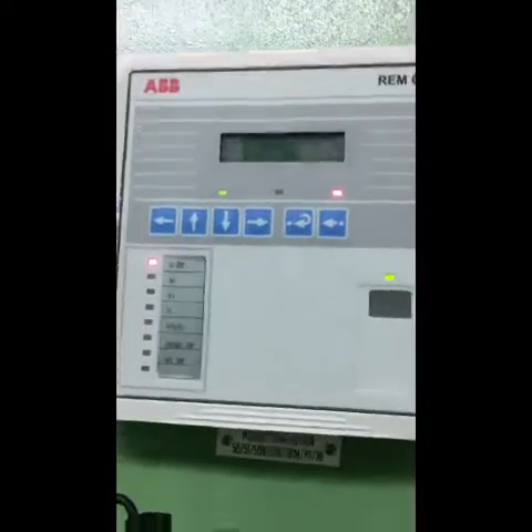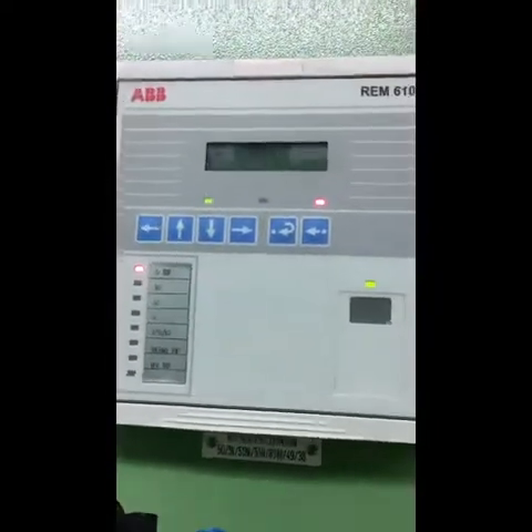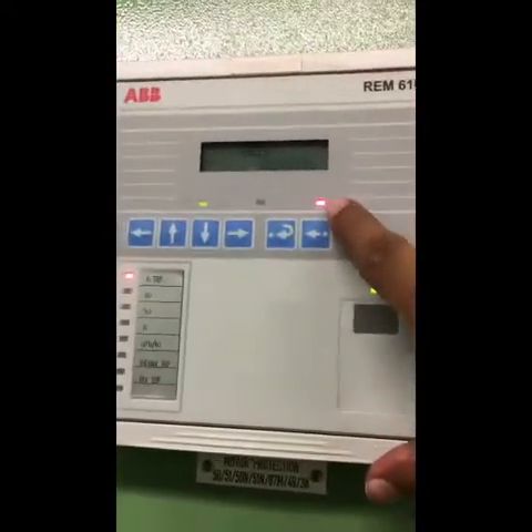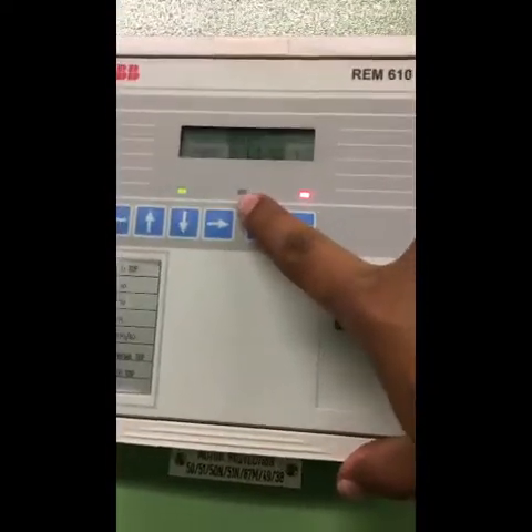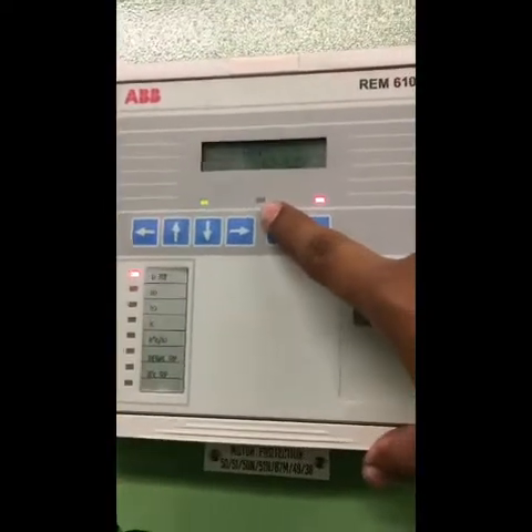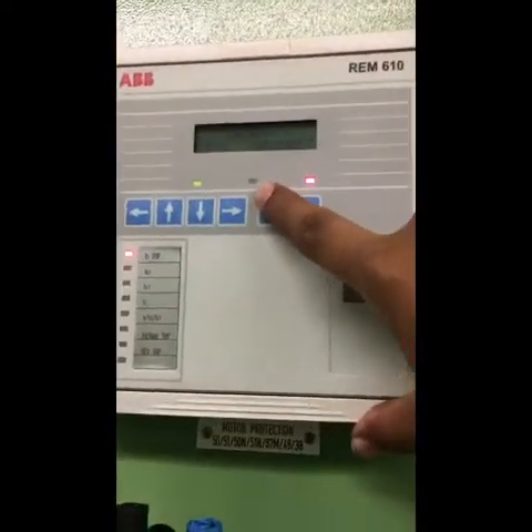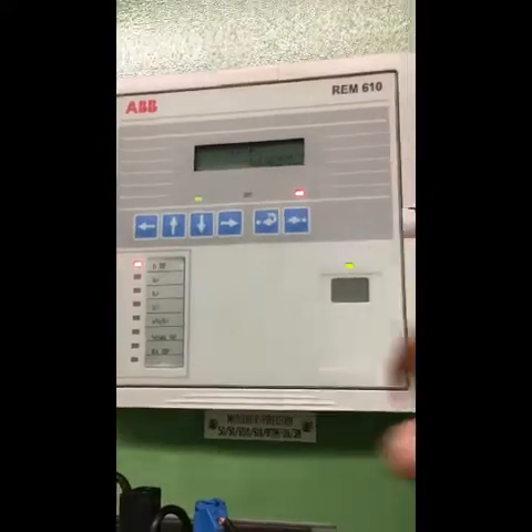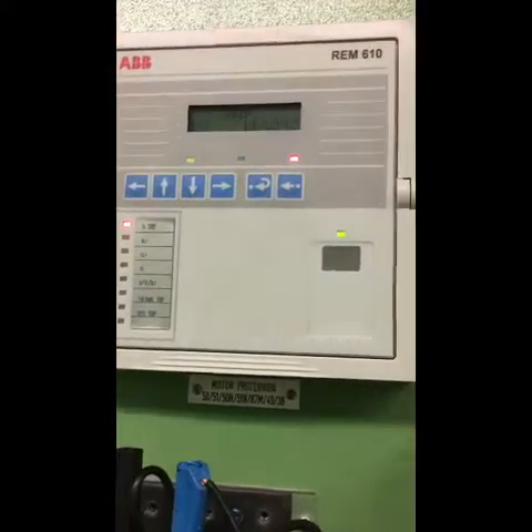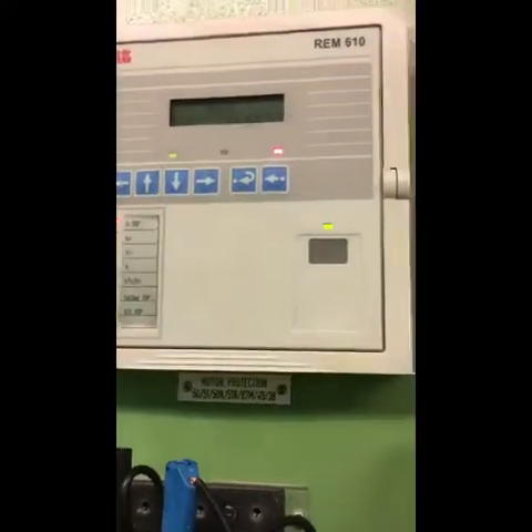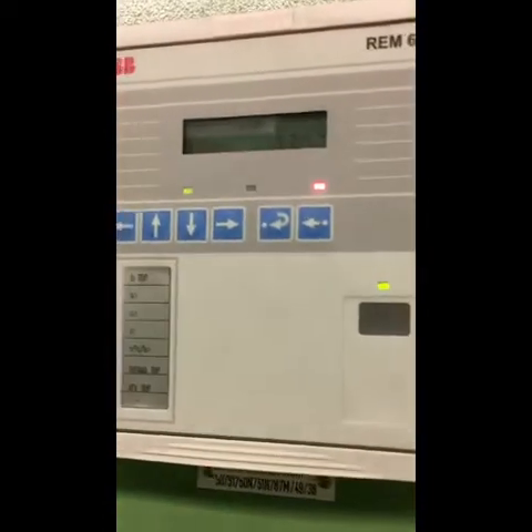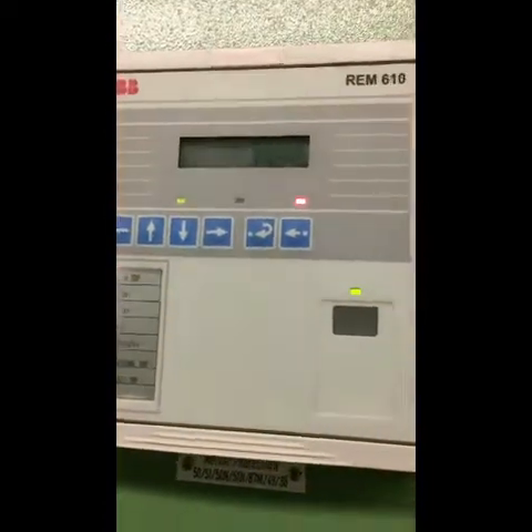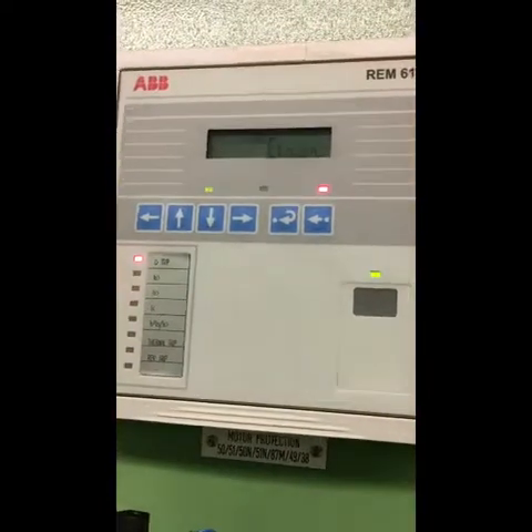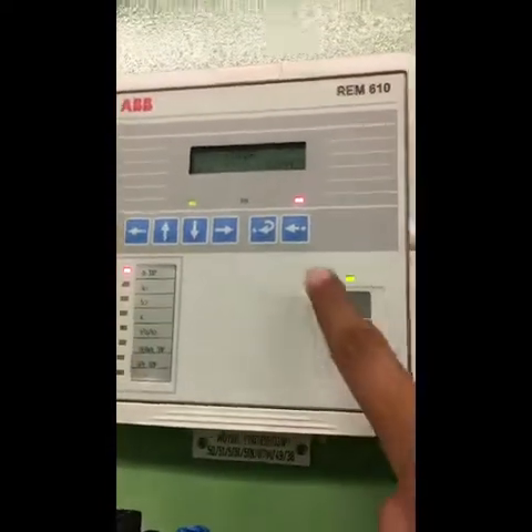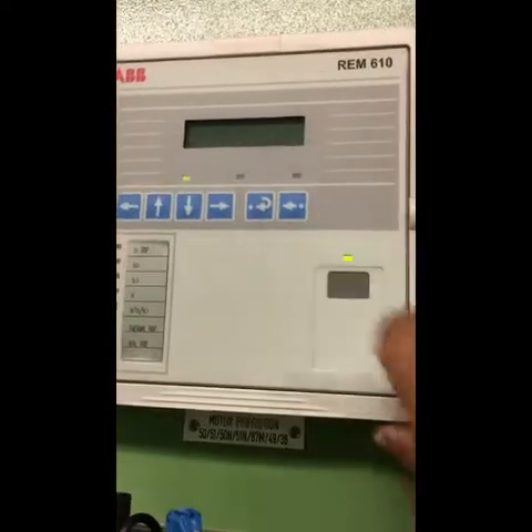We have a fault here. A trip signal came. This one is for trip, and this one will indicate yellow color, yellow LED, if there is any alarm, or if I am going to a fault soon. So this breaker tripped by overcurrent. To reset the overcurrent fault, we will press the reset button, which is this one.